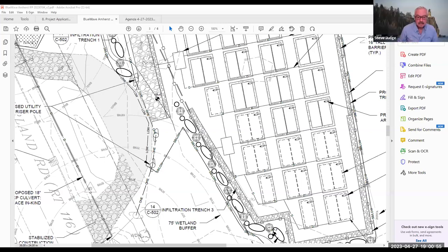The underlying cause for the additional poles is that Eversource's first three poles coming off the road will actually be owned by Eversource, with their equipment on it. From that last pole, referred to as the point of common coupling, everything onward will be Blue Wave owned equipment. The other three poles closer to the battery system will mirror the Eversource equipment on our side.